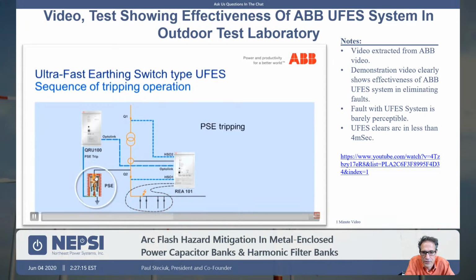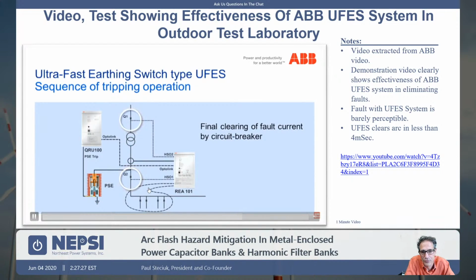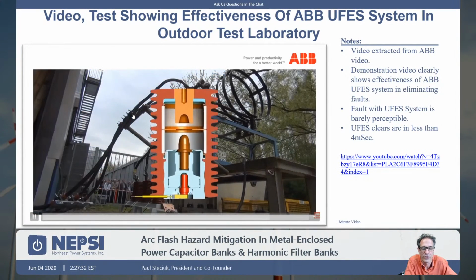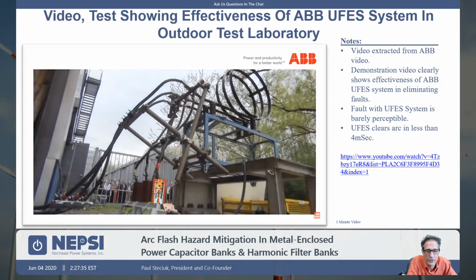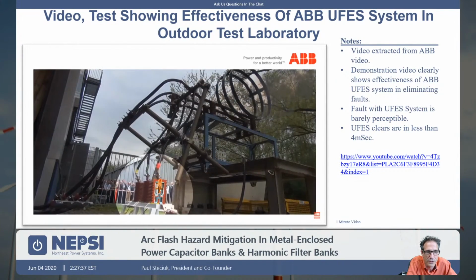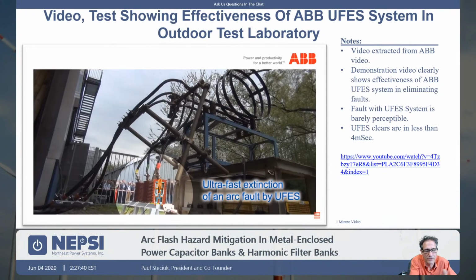When the fault occurs, the power switching units here close, which then creates a 3-phase bolted fault. In a sense, you're shorting out the arcing fault that occurred over here. And then you interrupt that fault with the upstream breaker. So you're shorting out the arcing fault and replacing it with a 3-phase bolted fault that eliminates the arc. You can see from the video, basically it's gone. It happens all within 4 milliseconds. Very, very fast. And there is a cost for this. It's not inexpensive.